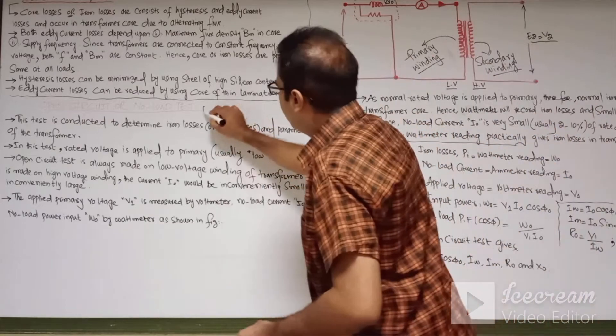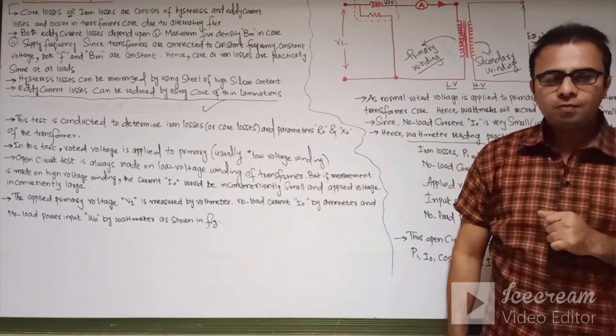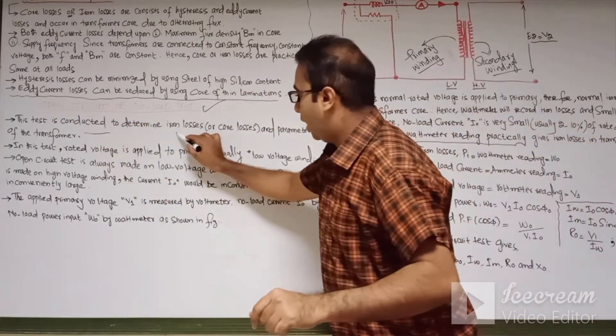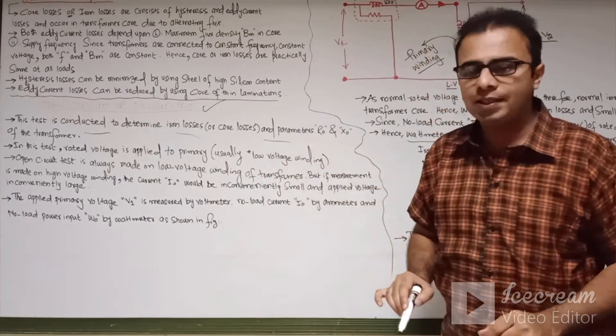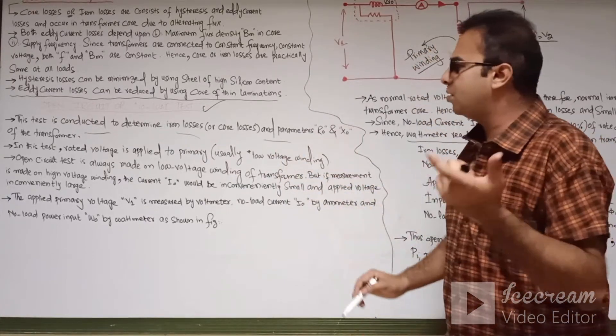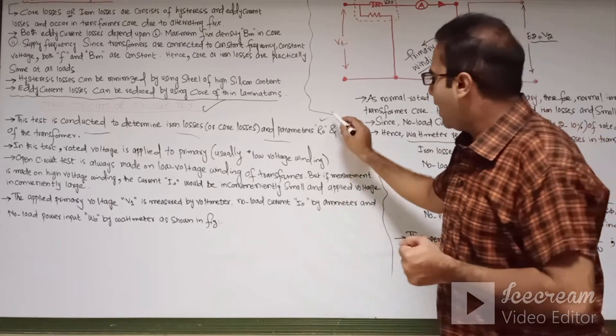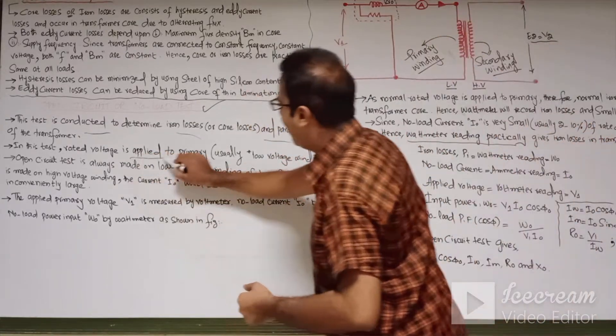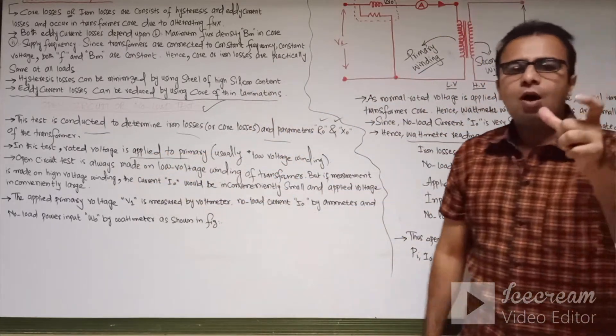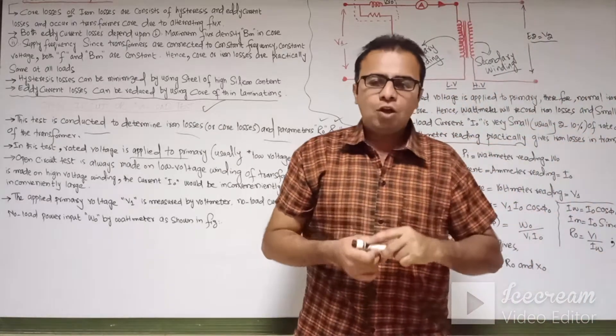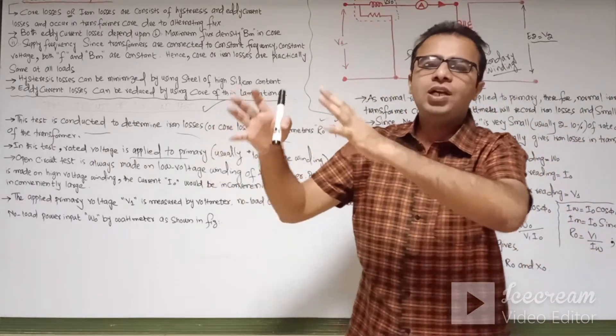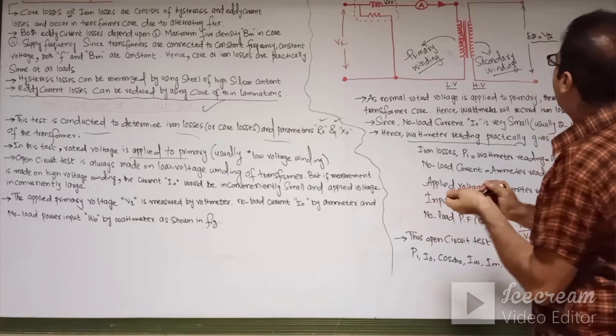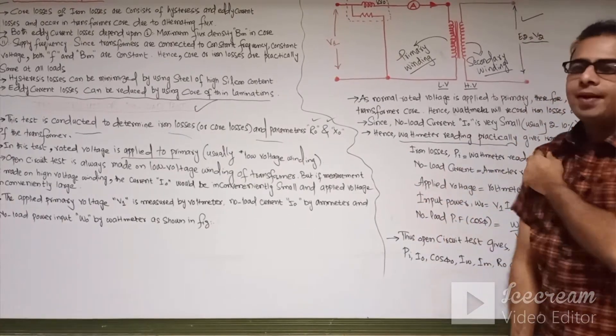Now let us discuss the open circuit test of the transformer. This test is conducted to determine the iron losses or core losses in the transformer, and from it we can also find out the parameters R0 and X0 of the transformer. In this test, rated voltage is applied to the low voltage winding of the transformer, and the high voltage winding is kept open circuited.